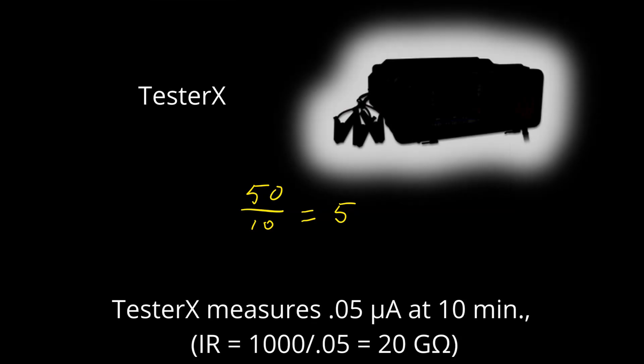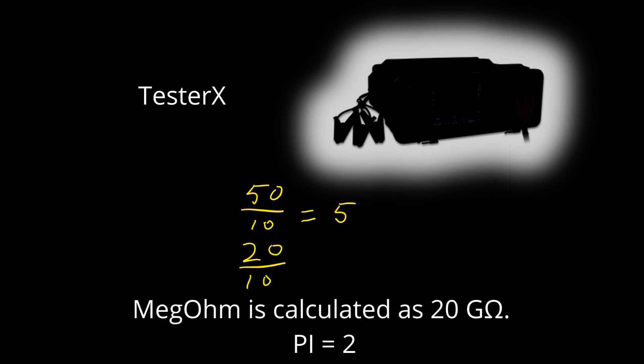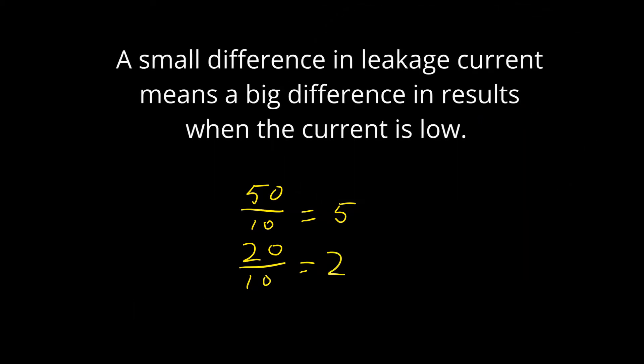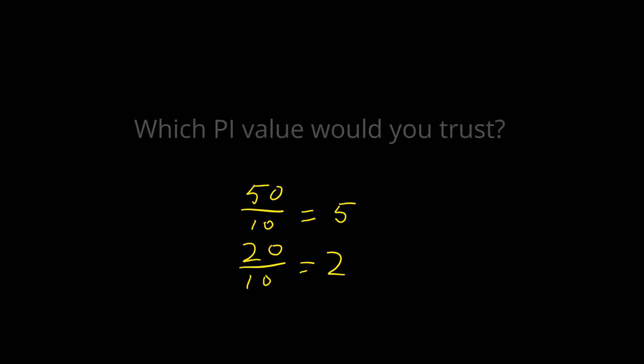Let's say tester X measures 0.05 microamps, a level at which it is not accurate. In physical terms, 0.05 versus 0.02 microamps is a small difference in current, but IR equals 20 gigaohms, or PI equals 2. The effect on PI is dramatic. A small difference in leakage current means a big difference in results when the current is low. Which PI value would you trust?